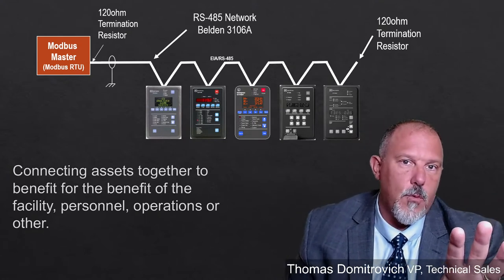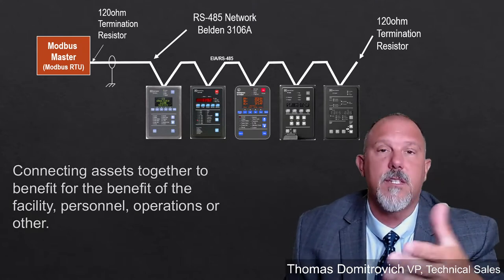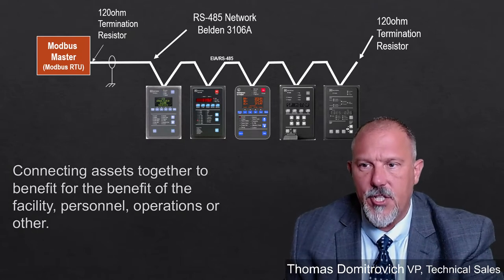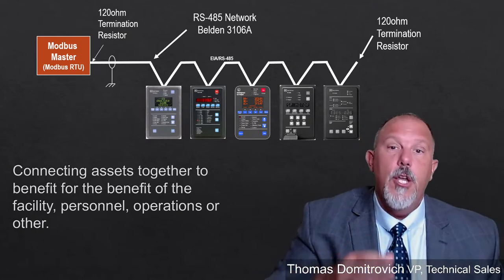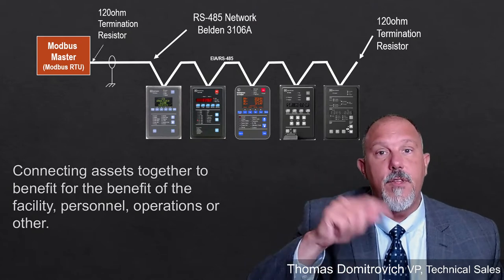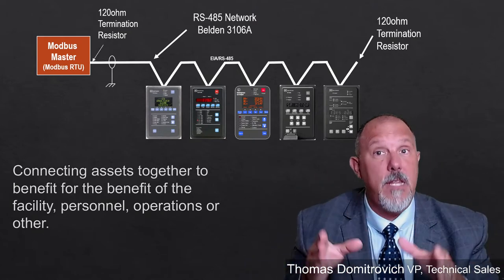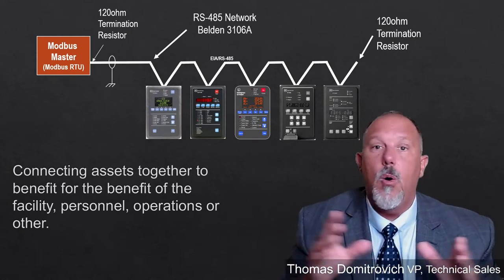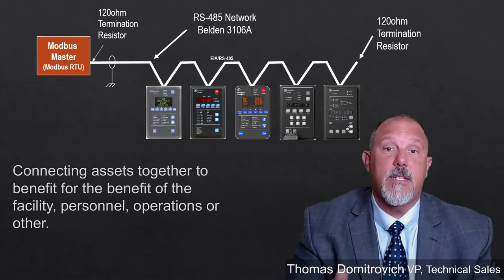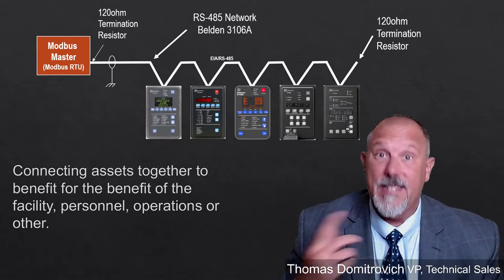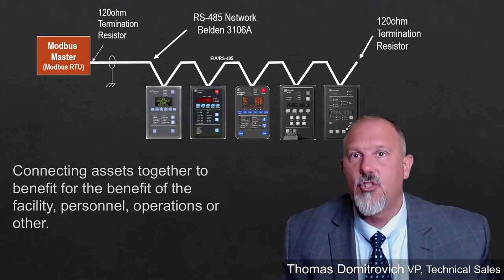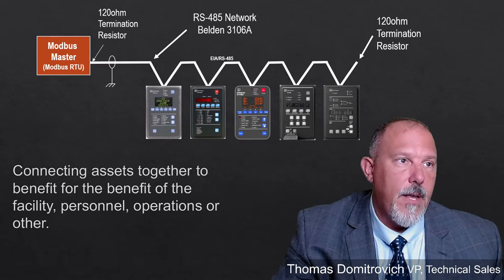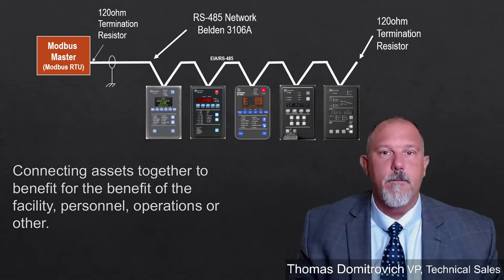And I'm pointing to an RS-485 network, so I could say this is a Modbus application. In many cases, it's a switch on the device you turn. Exactly, JW. You could have a switch on there that you turn on and off to tell it's the last resistor. So it will depend upon the manufacturer. The manufacturer may tell you, hey, I have the terminating resistor on every one of my devices, or you need to put one in. I've worked on systems in the past where we had to carry resistors and take a trip to Radio Shack to go get one. But it will vary by manufacturer.